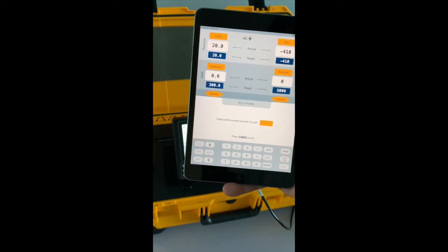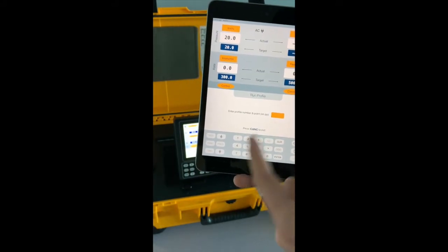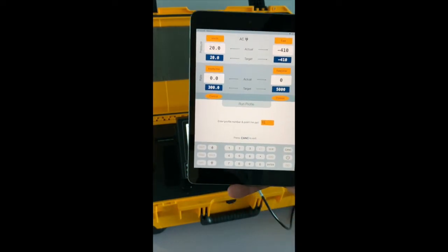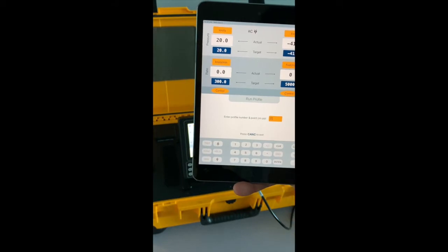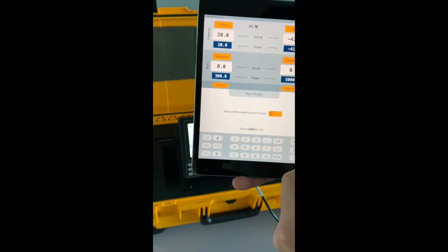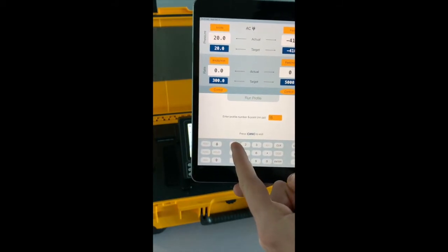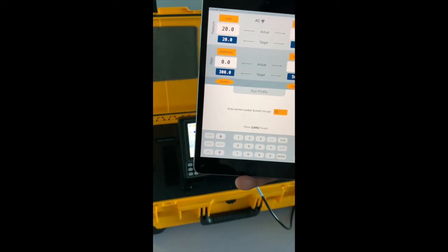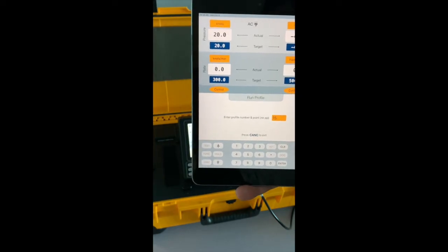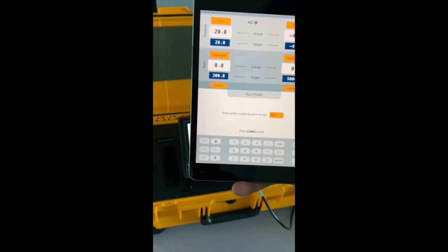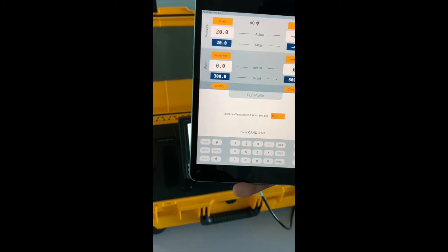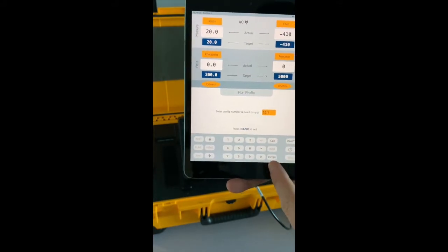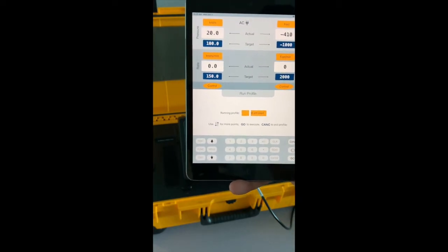The way to launch that is by pushing the profile number first. So let's say profile 15, then putting a dot, and then putting the step number. So you can start at step number 1. You can start at step number 20 if you want, 30, or 32, 47. You can start at any step you want. If you need to restart a check that you have left because you had another emergency, you can start it at a later step.